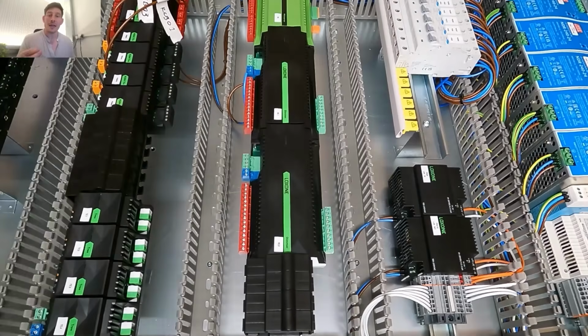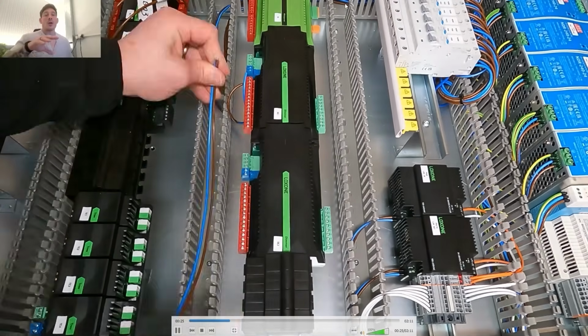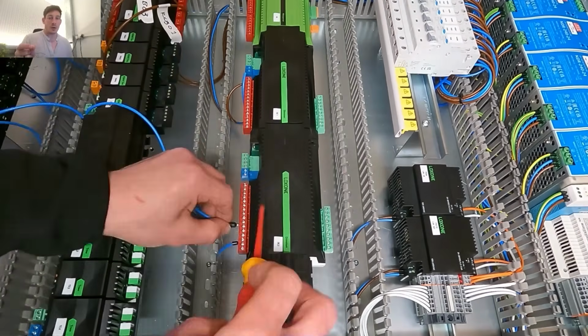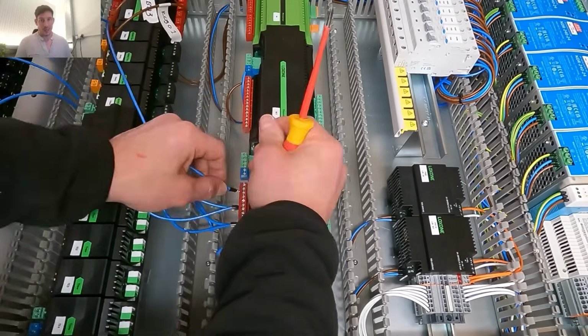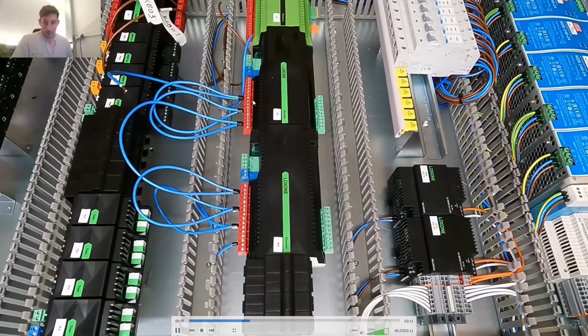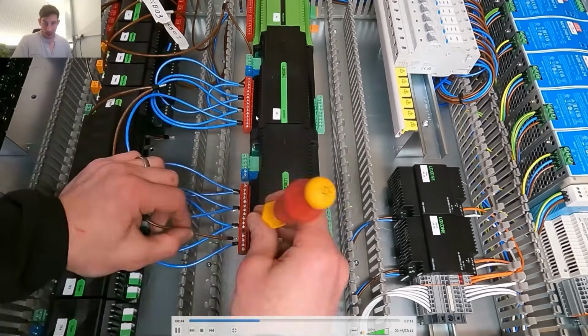This is the thing with the dimmer extensions - the neutral also goes into the module as well. The feed goes into the module and it also comes out, so it's important to do that. You can see I'm buzzing that neutral feed from the RCBO - that's exactly what I've done here across all of those feeds.